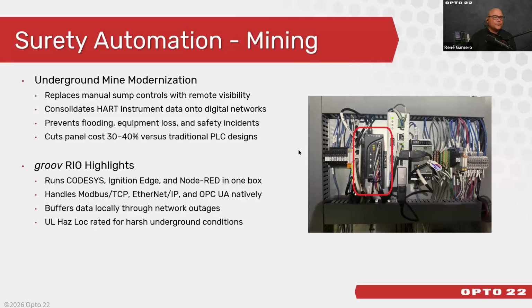And that's just one RIO device that's connected separately to another cabinet with the VSD, pulling in that data directly to IO. It's doing the PLC control, contextualizing the data, publishing it up, and now you're at over 100 of these units at this mine just performing this function. And they're just sprinkling RIOs throughout the facility, making a pretty incredible project for that systems integrator that started with just, I'm going to pull in these IO points, to now they're in dewatering systems.